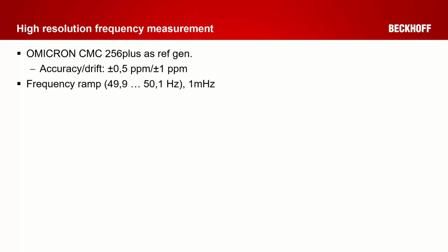Yes, now we come to another application I'm very interested in. I have some forwards. The grid can be supported by active power injection when a higher frequency change above a certain frequency level is detected. This kind of grid service to stabilize grids is required nowadays at wind farm control level. The basis of the realization is the quality of the frequency measurement in terms of resolution, accuracy, and update rate. So for this, I have built up a small test rig with a reference generator, our Omicron, with very fine accuracy and small drift, and programmed a frequency ramp with a small step change of 1 millihertz.